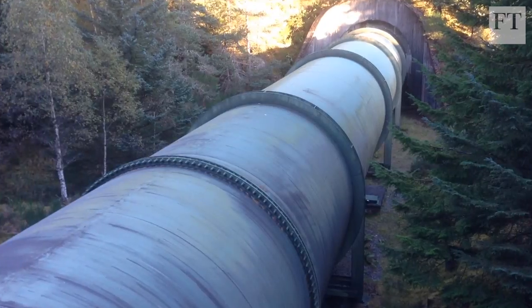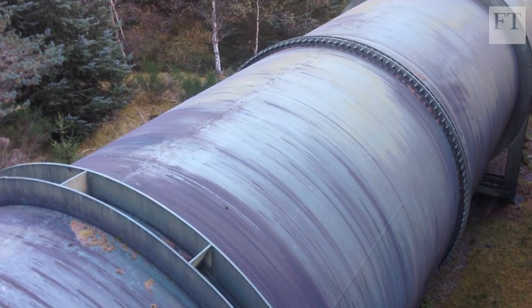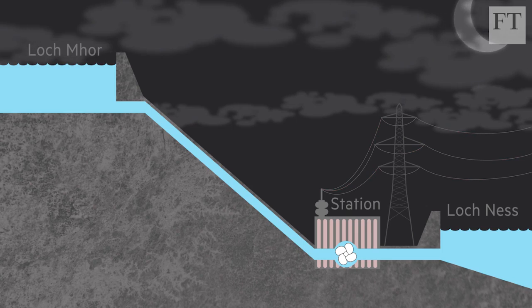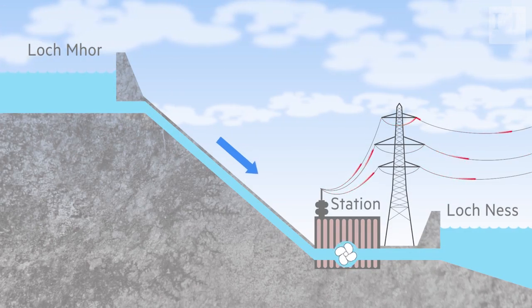The idea behind pumped storage is simple. A large pipe set under Loch Mhor's surface runs more than three kilometres through the mountains down to two turbines dug deep into the rock beside Loch Ness. When the grid has spare electricity, the turbines pump water up to be stored in Loch Mhor. When power is needed, the water flows back down to Loch Ness, generating up to 300 megawatts of electricity.